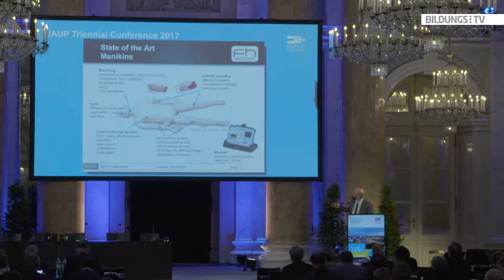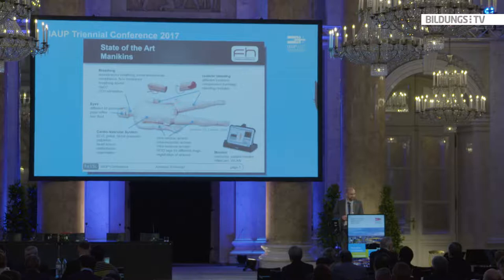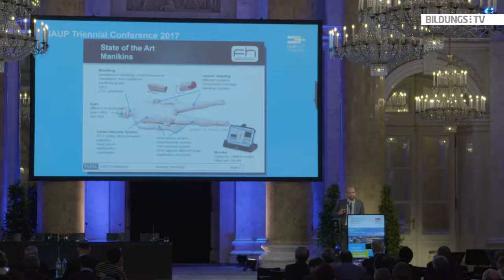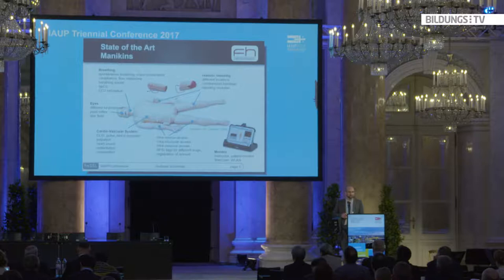It's also possible to have realistic bleeding. There are specialized modules simulating an amputee where real bleeding occurs and the intervention is to stop it. These full-size mannequins are controlled via a monitor typically over wireless LAN, where you can adjust different parameters and the simulator's behavior — and can spontaneously change the situation so the team of medical doctors must react correctly.